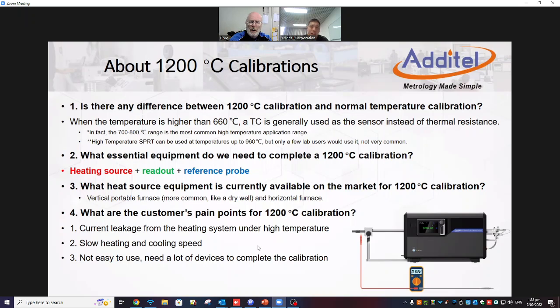So for thermocouple calibration, especially for temperature over 1,000, a horizontal furnace would be better. But that's not an absolute correct answer for everyone, because a few milli-K difference is okay, or it can be ignored by industrial customers, since their accuracy requirement is just like 1,000 milli-K or 500 milli-K. So they don't care about just a few milli-K.